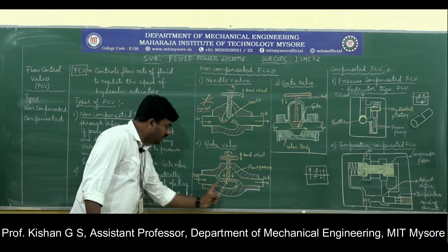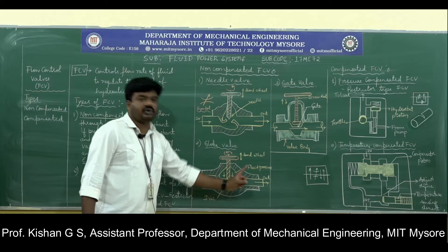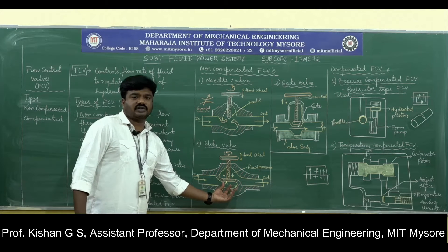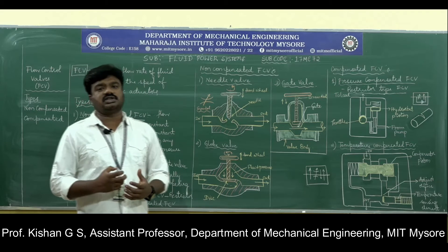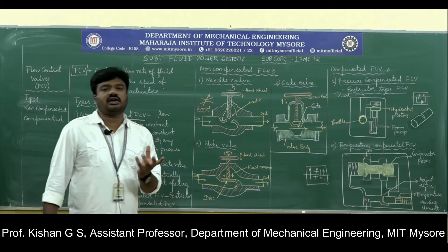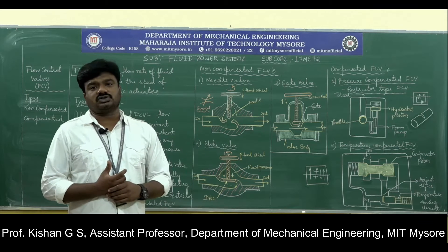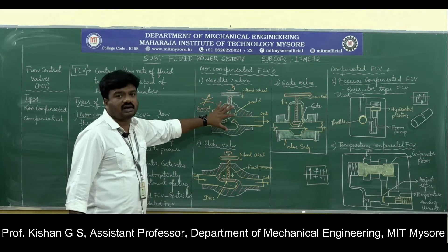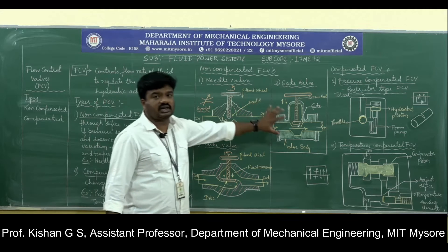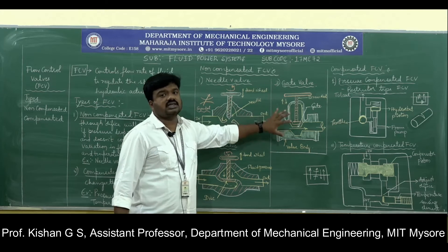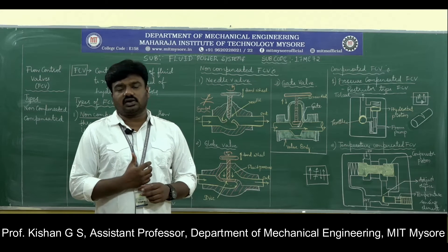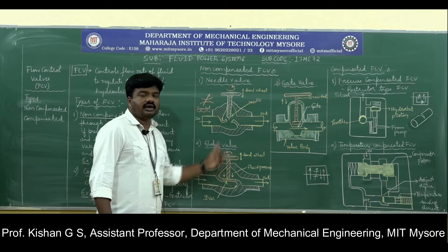In compensated flow control valve, whenever there is a variation in pressure or flow rate accountable due to pressure and temperature, the major parameter of concern is viscosity. Viscosity is one parameter in the fluid that is affected by pressure and temperature, since the same fluid is used for multiple working cycles throughout the hydraulic system. The variation in viscosity due to pressure and temperature is accounted for by automatically changing the valve adjustment opening.